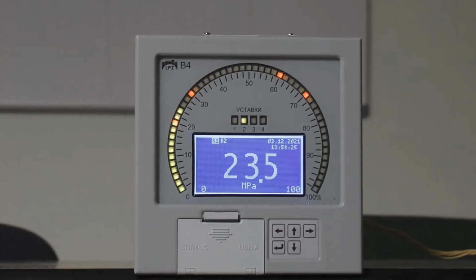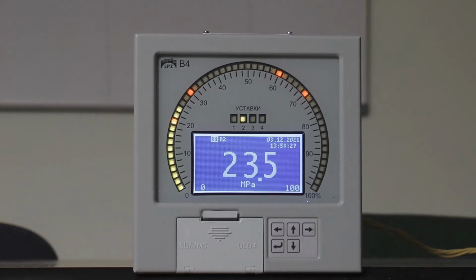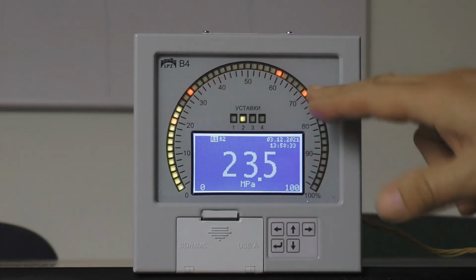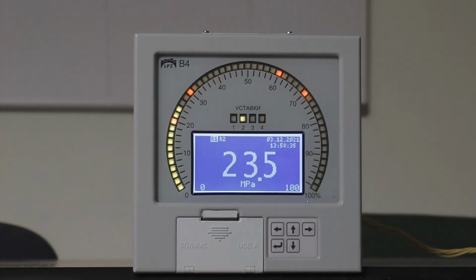B4 is an absolutely digital one. Its indication elements are a bicolor LED semicircular bar graph with highlighted set points. Also, there are 4 LEDs of set points and a graphic display. The graphic display shows exact values of the measured parameter, relay state like R1 and R2, date, time, start and end of the range, and the units of measurement.